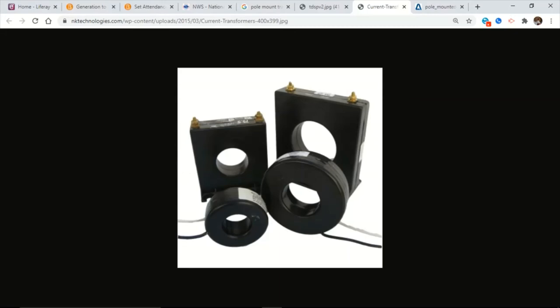So if we apply a voltage to this, let's take the primary side of 7,200. If we apply 7,200 volts in this image for figure 13-1, and our ratio is 4 to 1, what's the voltage going to be on my secondary 250 turn side? 1,800. 7,200 divided by 4 equals 1,800 volts. There you go.